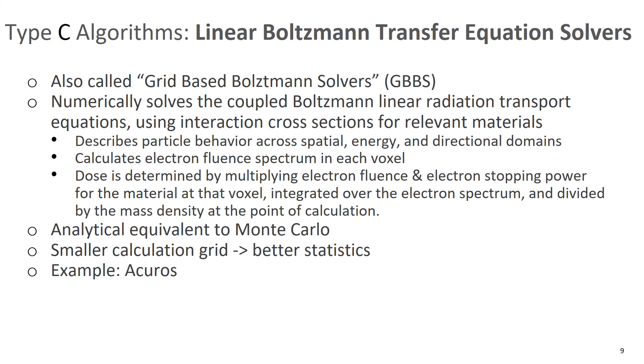So linear Boltzmann transfer equation solvers. These are newer on the scene. They're also called grid based Boltzmann solvers. Basically, it numerically solves the coupled Boltzmann linear radiation transport equations using interaction cross sections for relevant materials. So this is an analytical equivalent to Monte Carlo, like a numerical solver equivalent to Monte Carlo.